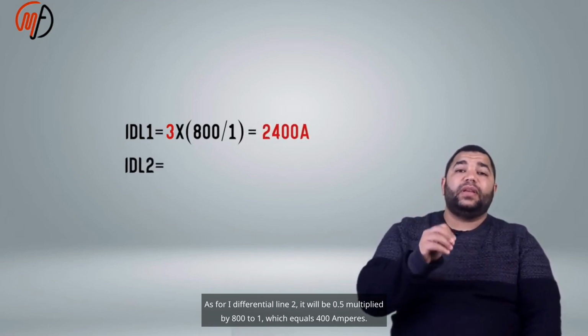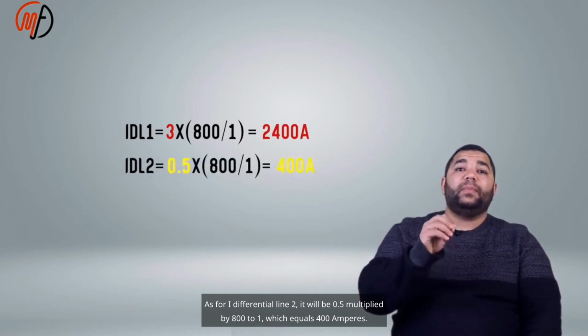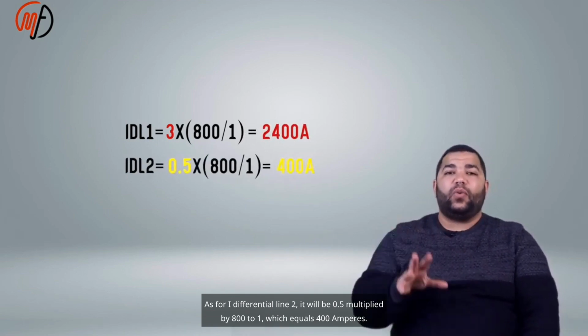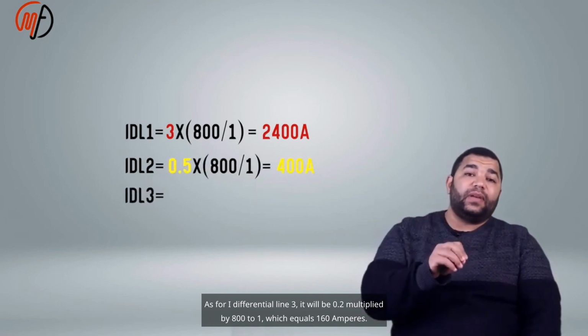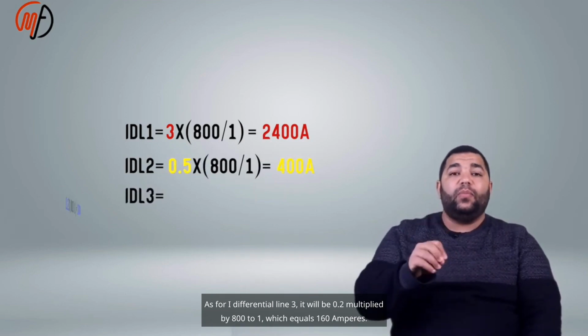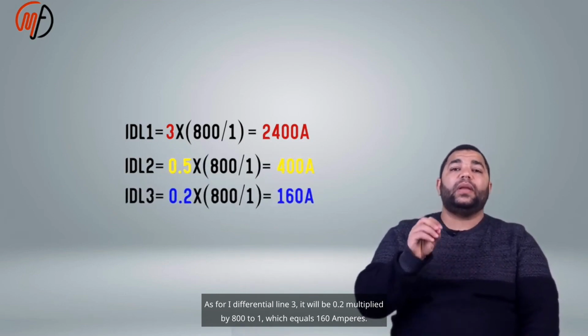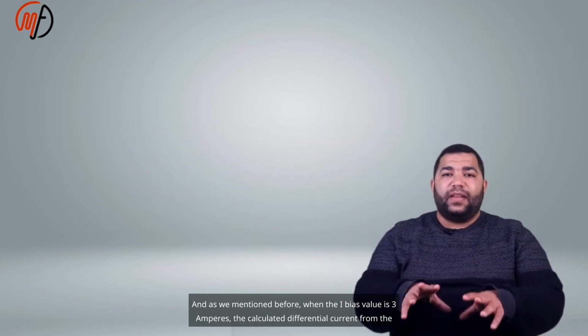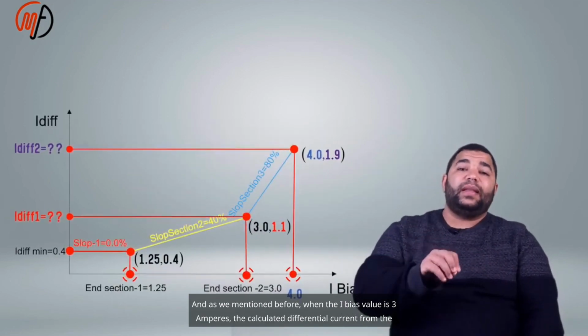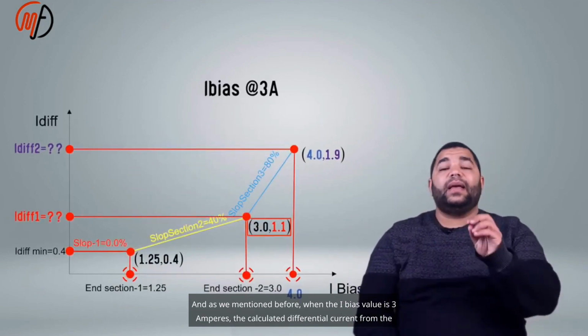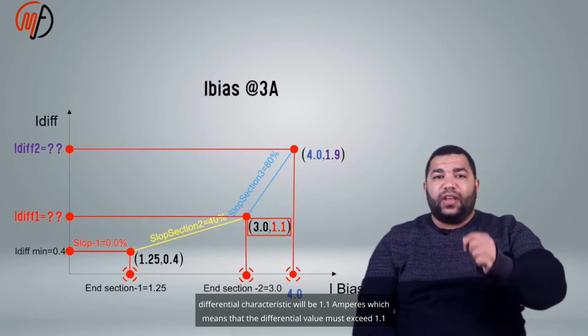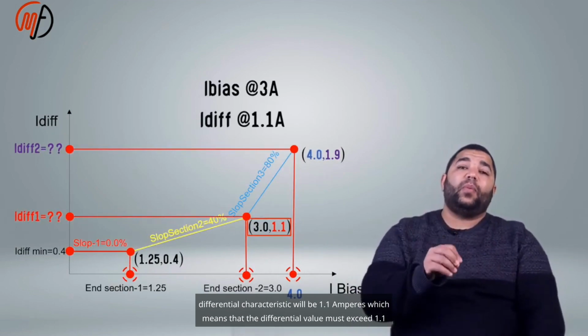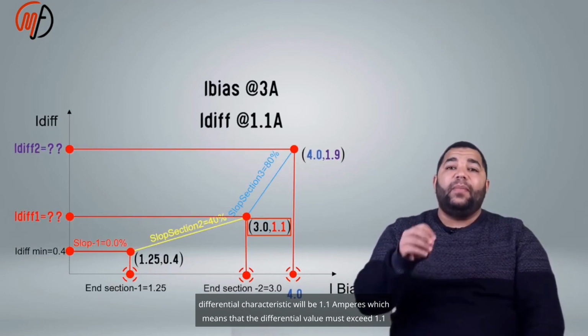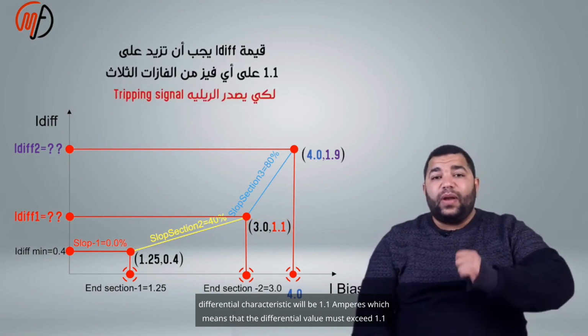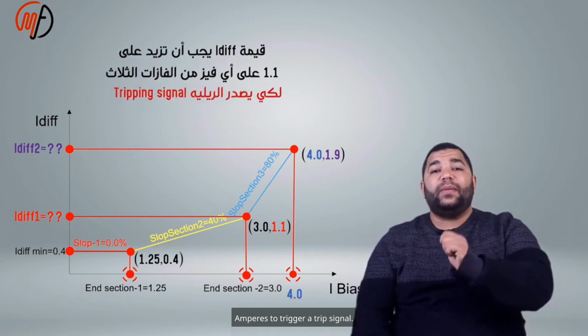As for I differential line 2, it will be 0.5 multiplied by 800 to 1, which equals 400 amperes. As for I differential line 3, it will be 0.2 multiplied by 800 to 1, which equals 160 amperes. And as we mentioned before, when the I bias value is 3 amperes, the calculated differential current from the differential characteristic will be 1.1 amperes, which means that the differential value must exceed 1.1 amperes to trigger a trip signal.